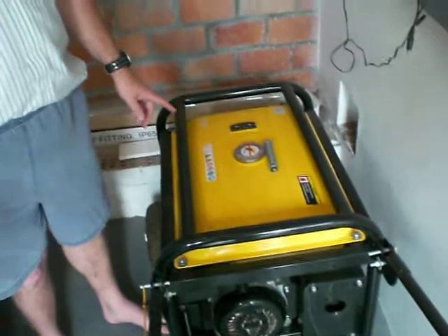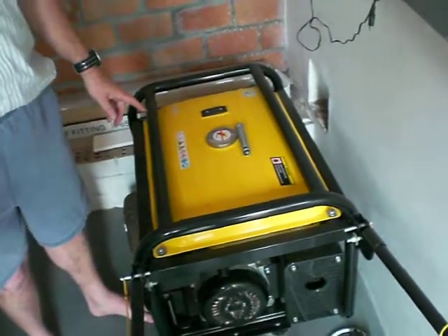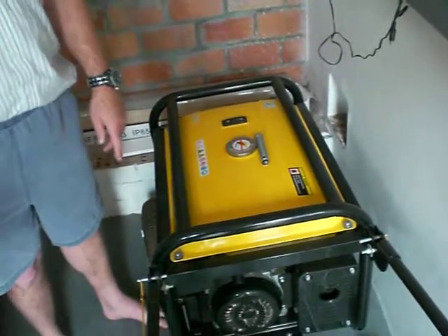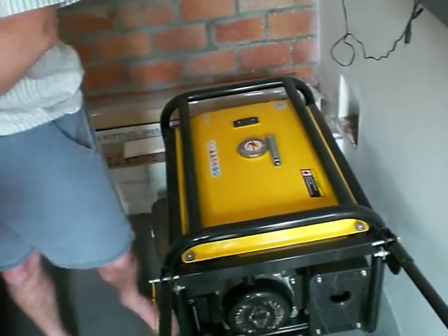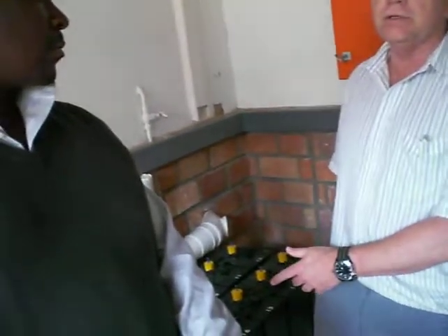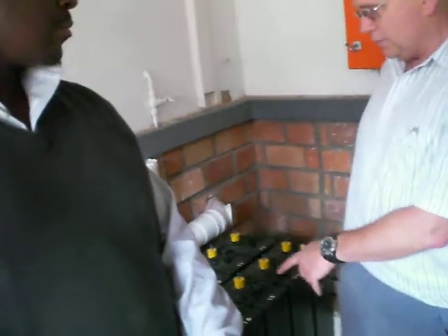The power went off at 2 o'clock in the afternoon. So that was before you put the system on? No, the system was in. So this is about a year ago. The power went off, so the system took over. This will give you about 25 kilowatt hours, down to 50% of the capacity of the batteries.